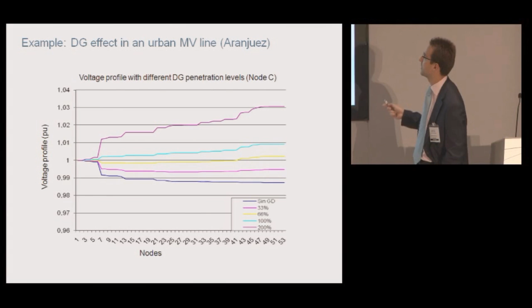In this first graph, we have done it for different penetration levels of this distributed generation located at point C, at the end of the feeder. You can see the first example that we were talking about before. So when we are injecting active power into the medium voltage grid, the voltage profile rises. In this case, it is more or less 3 to 4% up voltage.